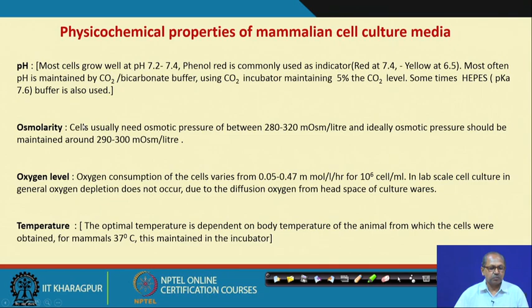Osmolarity is generally maintained between 280 and 320 milliosmol per liter, and the oxygen level is very important, because oxygen consumption rate depends upon the cell type. It varies between 0.05 and 0.47 millimole per liter per hour for 10 to the power 6 cells per ml. But for stem cell culture, the oxygen requirement is a little bit less, so you may have to maintain a lower oxygen concentration. Temperature you have to maintain at 37 degree centigrade. All these things, at least pH, osmolarity, oxygen levels, temperature and humidity, are maintained using a carbon dioxide incubator.